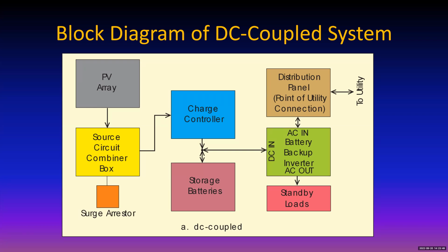And so then these loads get their choice of whether they need it, and if they don't need it, then it goes back to utility. So you notice the bidirectional arrows in several of the areas here. If the utility goes down, then that link between the green inverter and the distribution panel is opened up. And the rest of the system operates by itself.